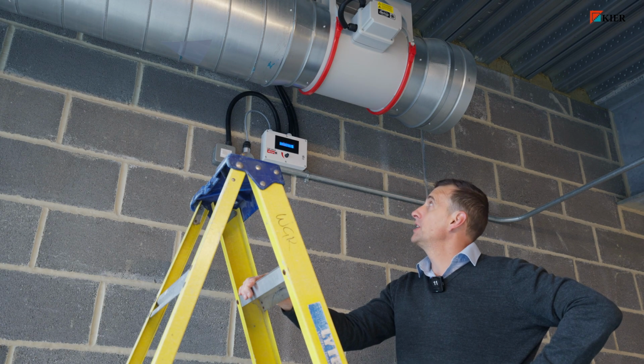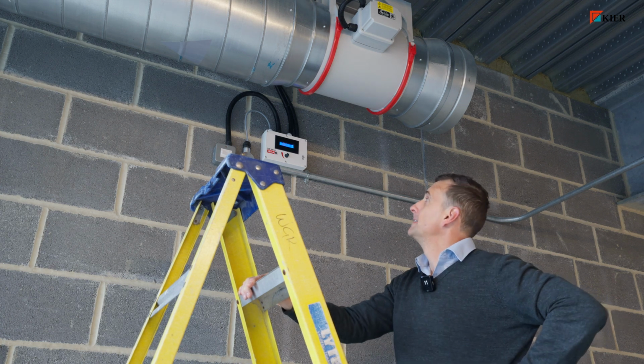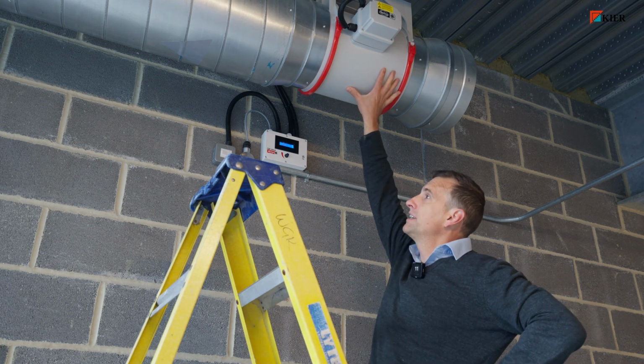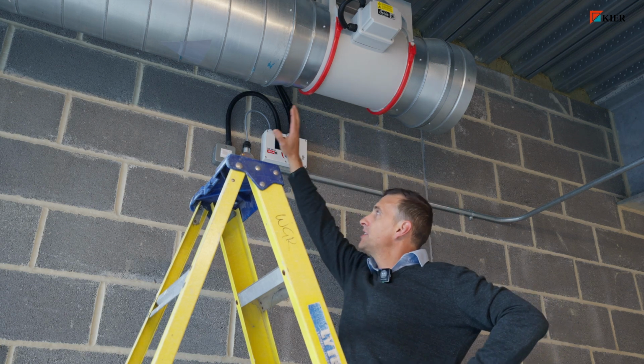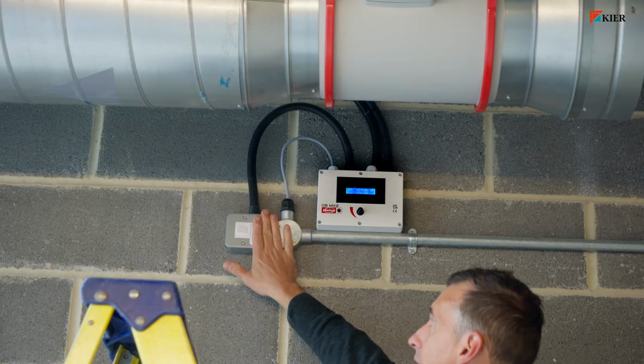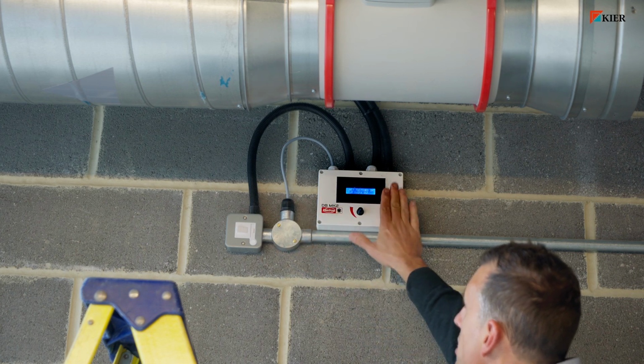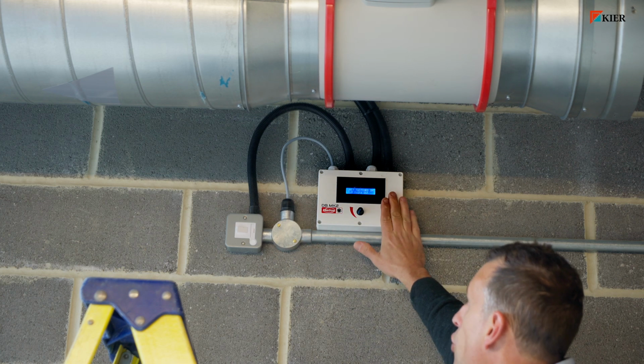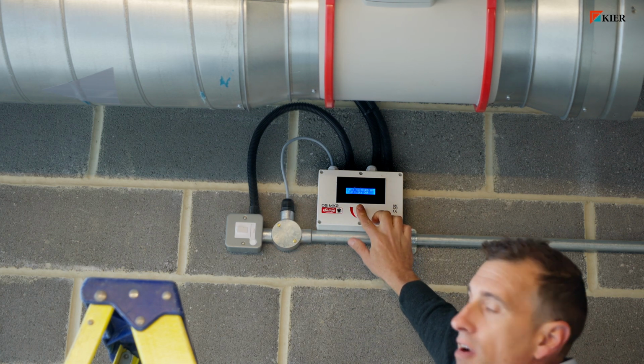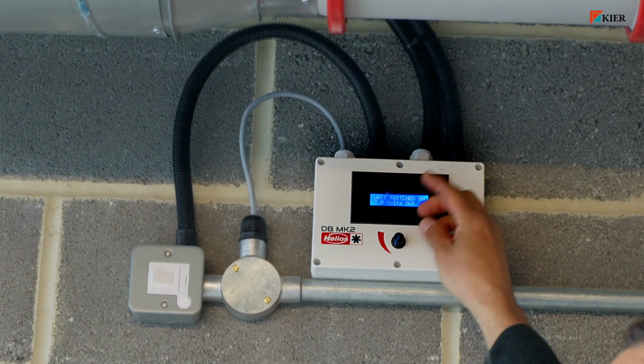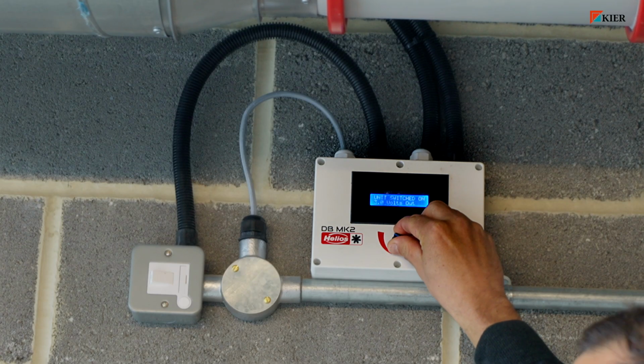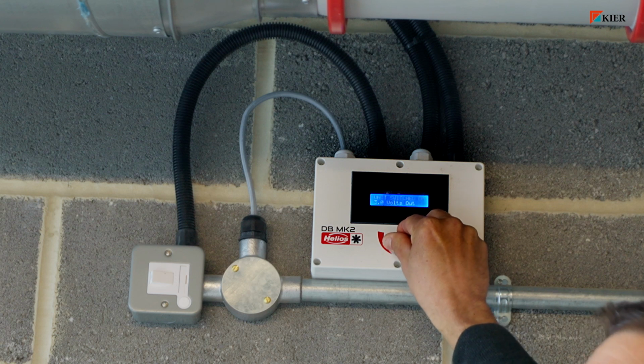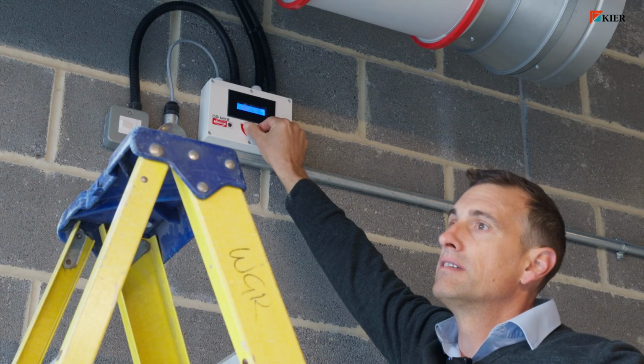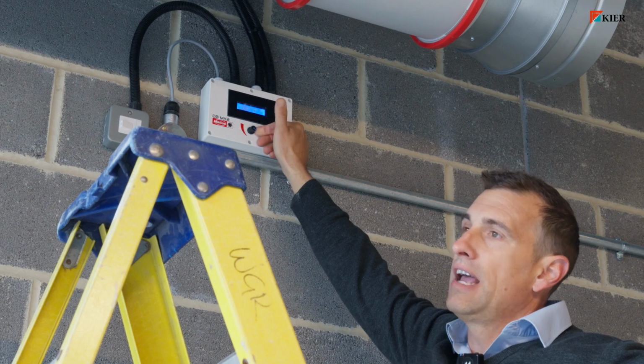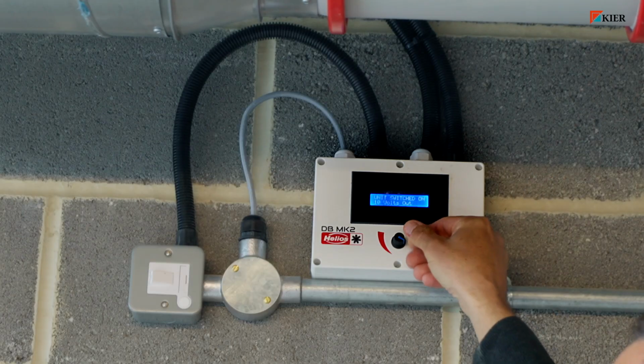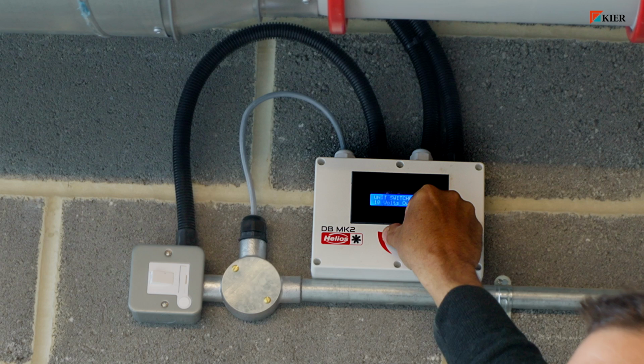This demonstration is for the bin store extract fan. The extract fan is located inline, it's an inline fan. The means of isolation, electrical isolation, is done at the spur, and the adjustments on the fan speed are done at this controller. So at the moment the fan is running very, very low, but if you want to increase it, it's just merely turning this dial and you'll hear the fan increase in speed. If you want to dial it back down, it's just merely turning it in an anti-clockwise direction.